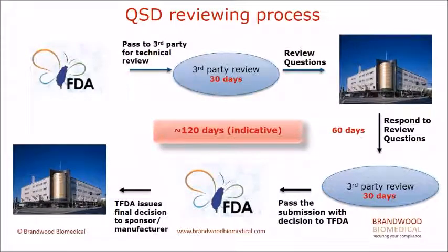Let's go through the reviewing process for QSD applications. So once the application lodged to Taiwan FDA, the responsible reviewer will do a high-level review to ensure all documents have been provided. Then we'll pass on the submission to a third party to conduct clinical review. According to Taiwan FDA indicative timeline, the manufacturer are expected to hear back from the third party in 30 days and to respond to any review questions. The third party normally allows the manufacturer or sponsor 60 days to provide response to any review questions.